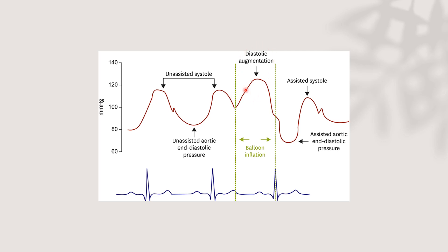The augmented diastolic pressure rises above the unassisted systolic pressure. At the end of diastole, the balloon deflates, lowering the aortic end-diastolic pressure — this is the assisted end-diastolic pressure. The following assisted systole is then lower than the unassisted systole. So during inflation the balloon produces supra-systolic diastolic augmentation, while during deflation the assisted systole and assisted aortic end-diastolic pressure both decrease — allowing more ejection from the left ventricle and increasing cardiac output.